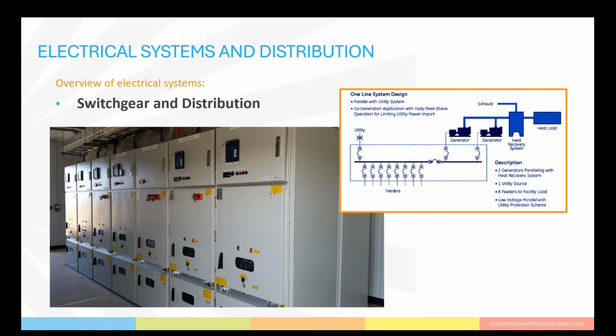In regard to the control compartments, there are 3 basic control compartments and a mimic panel, which is normally just a color touchscreen HMI that will display system 1 line status. Those control compartments are a master system control compartment, and there's 1 required per system. There's a generator control compartment, and there's 1 required per generator, and a utility control compartment, and there's one required per utility source.